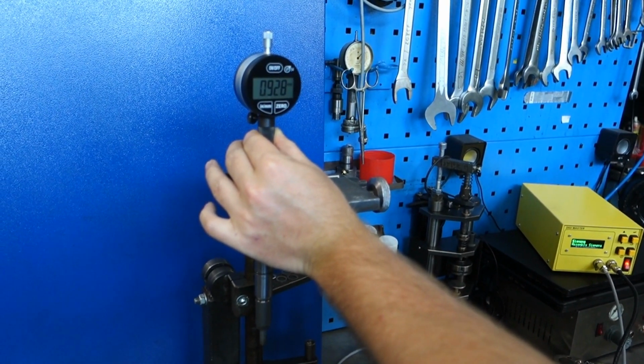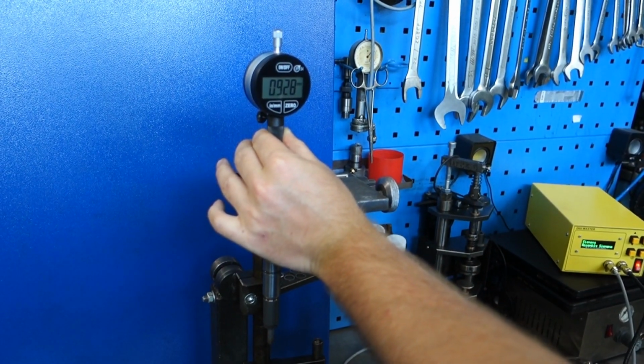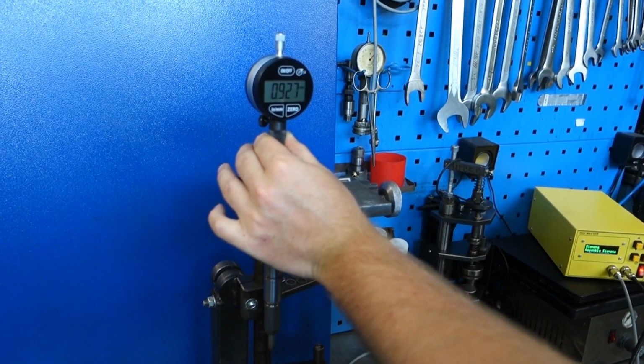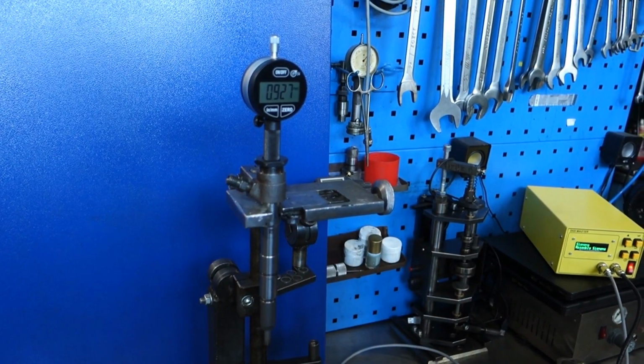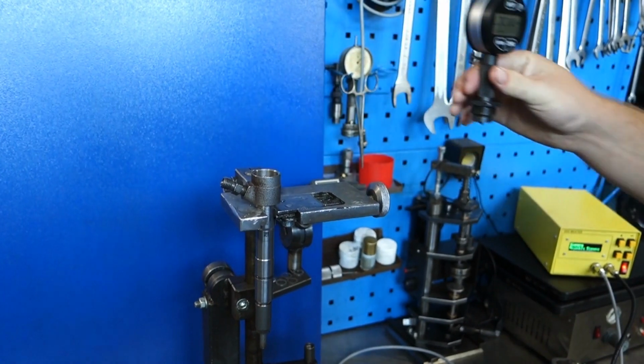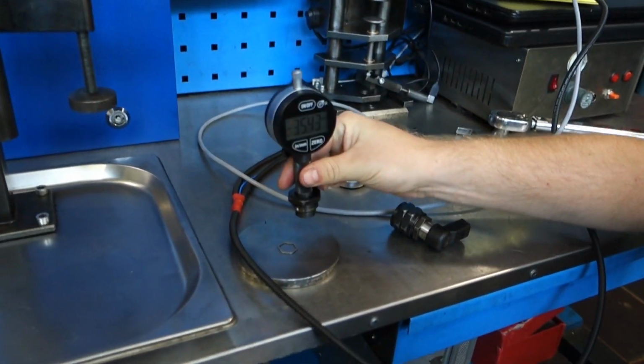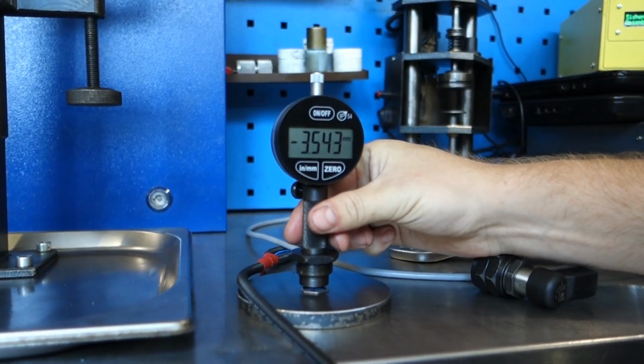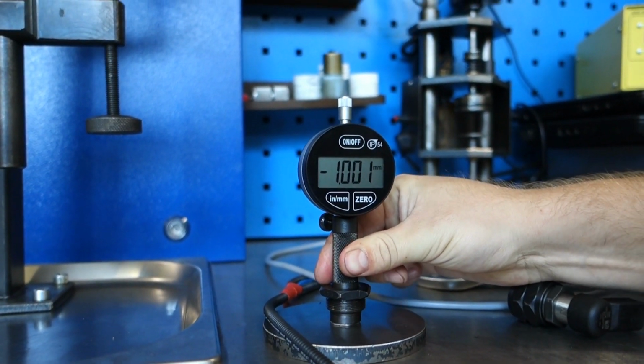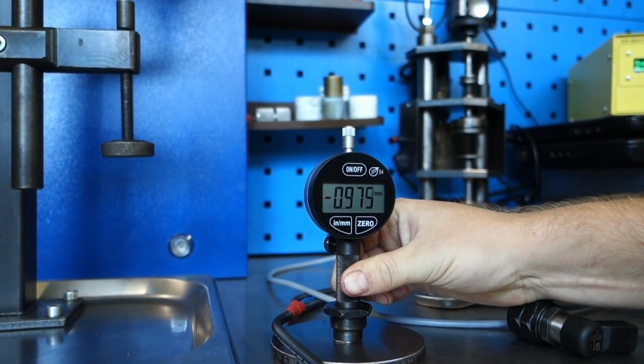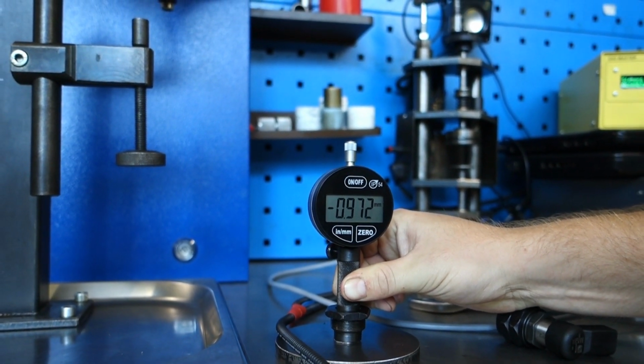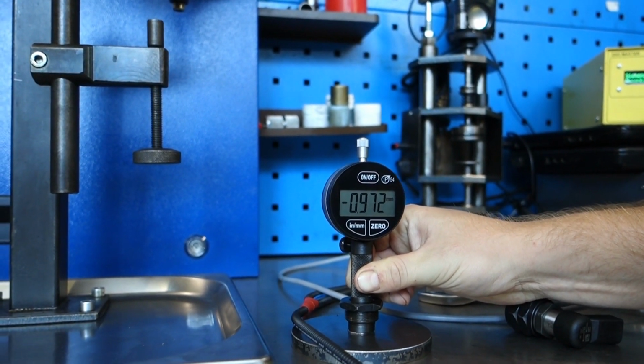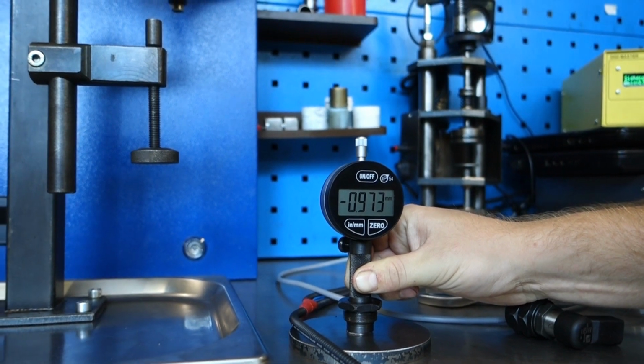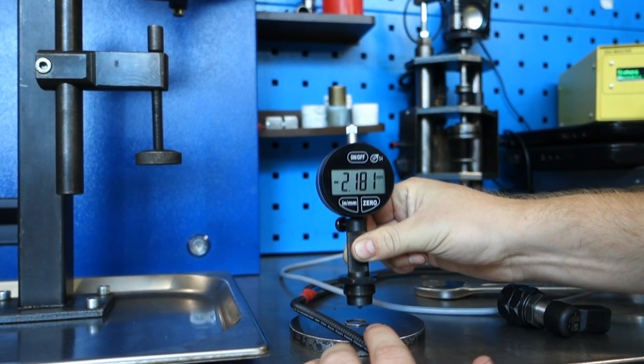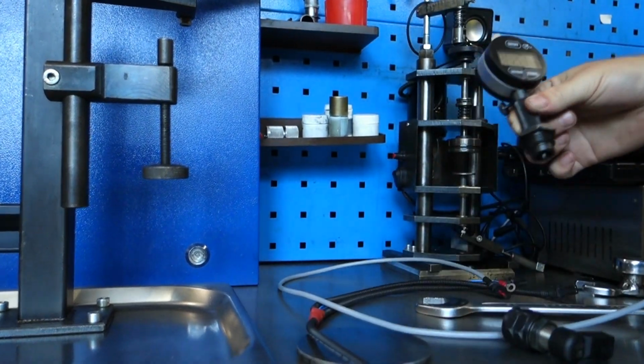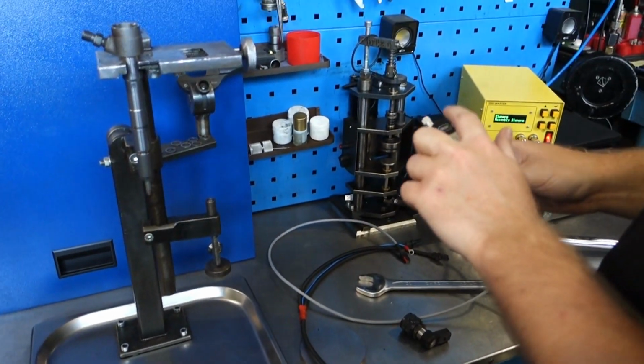So if we have 927, we need about, let's say, 960, maybe 950 something. Adding about 30, 20 microns is perfect. So we move over. As you can see, you can use the adapter to also measure your shims. As you can see, this shim is slightly bigger. It's about 40 microns, a little bit more, maybe about 45 microns higher. That's fine. The Digimaster will still be able to tell you whether it is correct or not.